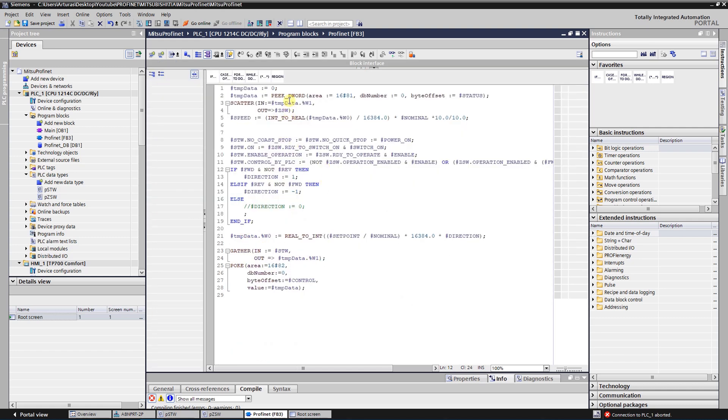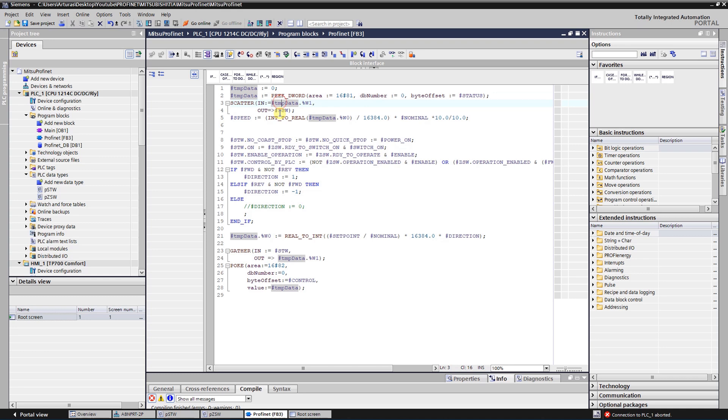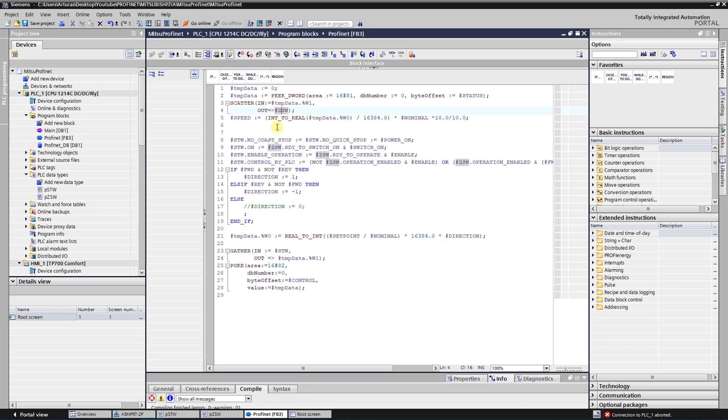First of all, I am reading the data from the VFD into my variable TMP data. Then I scatter word number one, where all the status bits are coded, and I save them into ZSW. That is basically an array of 16 bits. And as I have already mentioned, there is this calculation of the current speed by NSOLLA. So it will be setpoint.